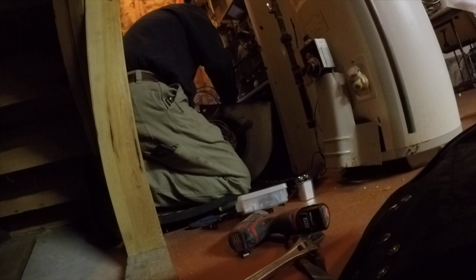At this point I have the blower wheel tightened onto the shaft of the new motor. Motor's installed. I'm fastening down the wires on the brand new capacitor — I always put a new capacitor on with the new motor. Now I'm going to try to get that blower housing back into the rails on each side and get it fastened in place.